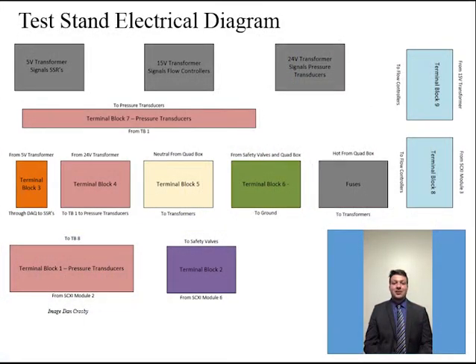Once the power leaves the electrical box and goes to the quad box, it is then sent to the top of the test stand. At the top of the test stand, the 120 volts AC, neutral goes into terminal block 5, ground into terminal block 6, and hot into the fuses. Once going through terminal blocks 5, 6, and the fuses, it is sent to the transformers. In the transformers, the 120 volts AC is converted to DC by going through the transformers and then a full bridge rectifier in each of the 3 transformers.